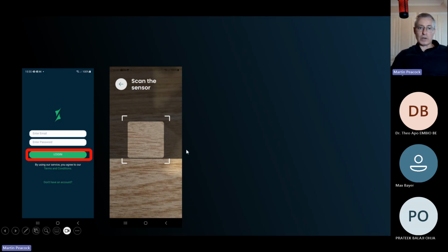I suspect that most of you will end up building either your own sensor or your own application upon one of our sensors. So, for example, if we have a potassium sensor, that's a very mature sensor for us, and it works perfectly well. But most of our work will be in potassium in blood or potassium in dialysis solution. Your potassium could be in runoff from a field or something. That is a different application and will end up with its own sample preparation and its own algorithm. If you're joining late, don't worry about it.